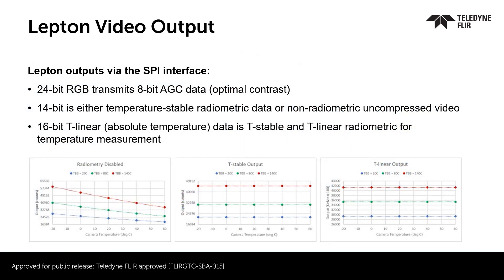The video output of Lepton has multiple formats and can come from different parts of the video pipeline. Lepton 2.5 and 3.5 are radiometric. When necessary, radiometry can be disabled. When it is disabled, the camera output is not necessarily linearly proportional to the output temperature because it's dependent on the temperature of the camera. When radiometry is enabled, the T-Stable output stabilizes the output of the camera. When T-Linear is enabled, which is by default, the output of the 16-bit interface is linearly proportional to scene temperature.